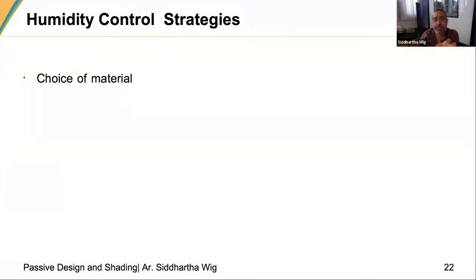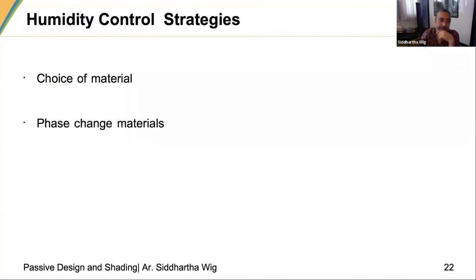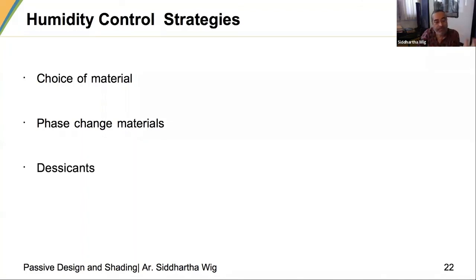For humidity control strategies, the choice of material matters — we have often used mud or a variation of mud with very little cement on walls to allow it to breathe. You can have phase change materials that actually change their phase depending on temperature and release that heat when they change back. You can also have desiccants, which are very popular, or a desiccant wheel — though that uses some energy and would come under the category of a hybrid system.